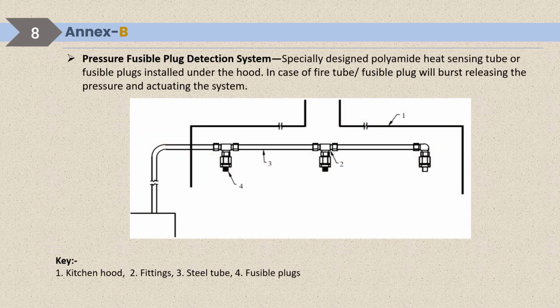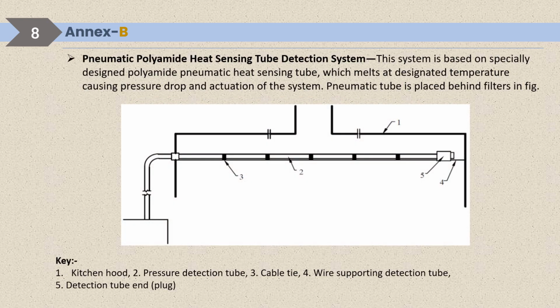Pressure fusible plug detection system: specially designed polyamide heat sensing tube or fusible plugs installed under the hood. In case of fire, the tube or fusible plugs will burst, releasing the pressure and actuating the system. So this system operates on fusible plugs. When a fusible plug bursts, that will actuate this system. Pneumatic polyamide heat sensing tube detection system: this system is based on a specially designed polyamide pneumatic heat sensing tube, which melts at designated temperatures, causing pressure drop and actuation of the system. The pneumatic tube is placed behind the filter as shown in the figure. So this is the arrangement. You can see how things are installed in the hood.